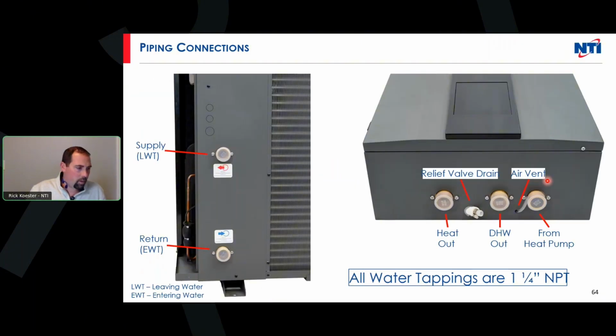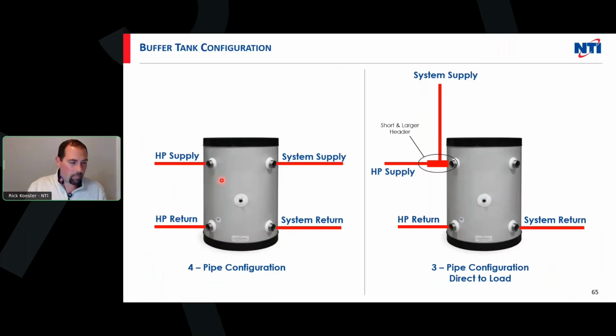All right, piping. All connections, whether it be the outdoor units or the indoor hydro box, are all 1.25" MPT tappings. So the contractor can put his choice of fitting on there, whether he's doing PEX, copper, whatever he chooses. If he has a flex line or vibration line coming off of this, he gets to pick the material. So we just want to give them something solid to come off with. The actual labels here, really nice. So identifying what's going to be our input in leaving water temp, so leaving and entering. So hopefully they don't screw that up and pipe it wrong, but it could happen. Obviously it can happen, but they do a good job of labeling these machines, so it prevents that.